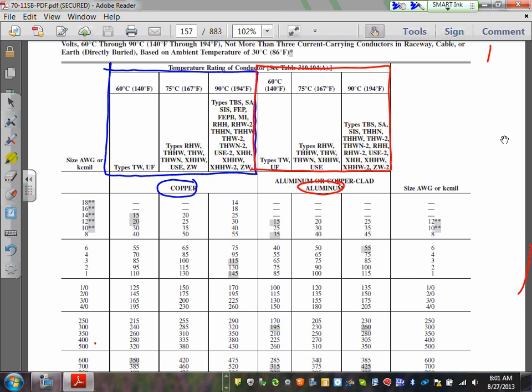As engineers, what do we prefer? Copper. Why copper? Copper is safer, smaller wire, safer to work with, better conductivity. Now as contractors, putting on the contractor's hat, what do we prefer? Aluminum. Why aluminum? Cheaper, easier to work with, lighter, bends better as cables, okay? But on all the engineering projects that I worked on, especially commercial industrial buildings, we specify feeders as copper feeders.